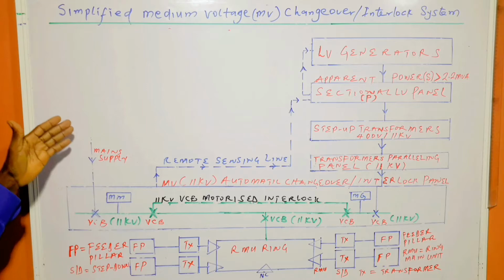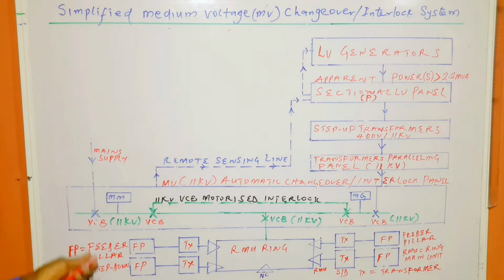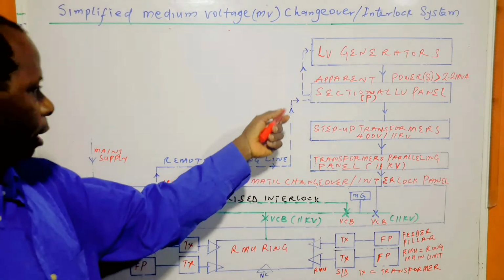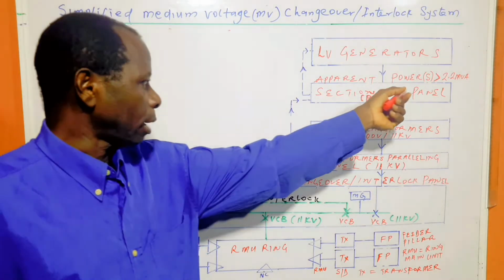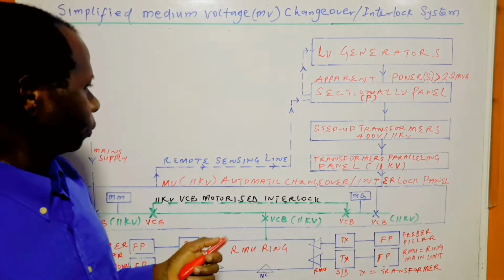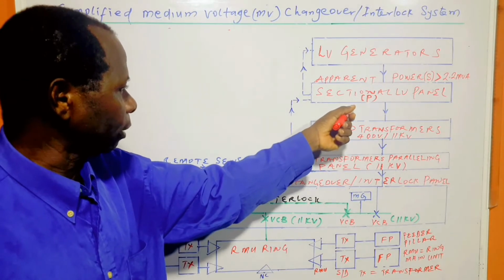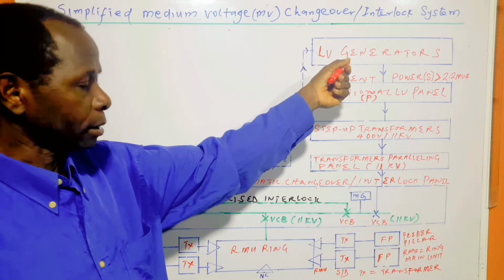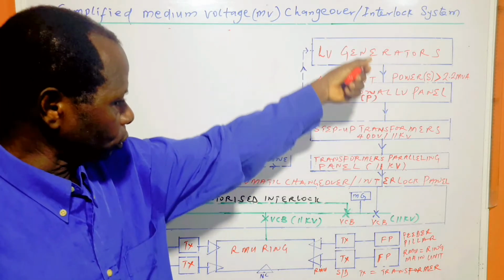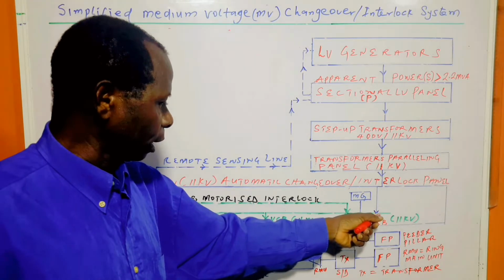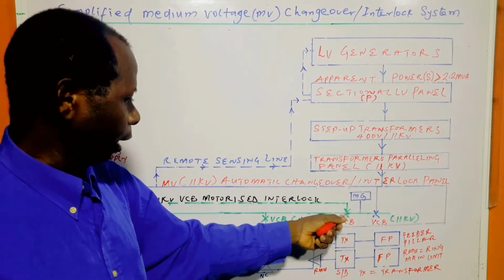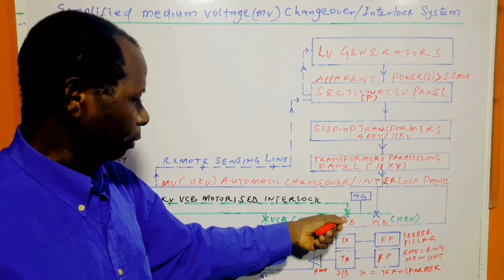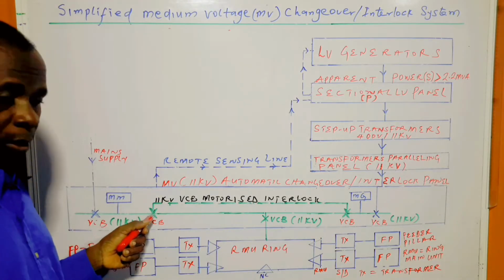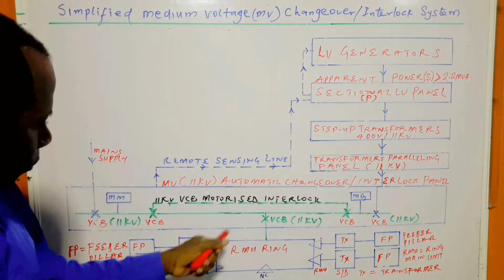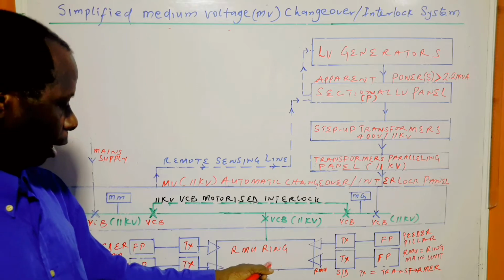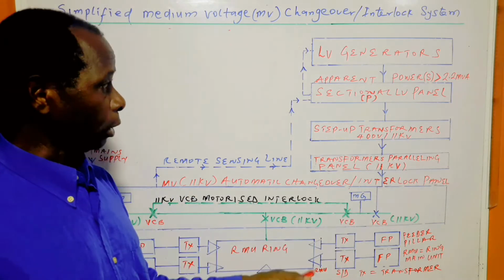And what happens is that immediately there is power interruption, this panel sends a signal through this remote sensing line to this sectional LV panel P, and this LV panel P signals the generators to start. So the generator will start and continue to supply power to the load through this vacuum circuit breaker. And when the power is delivered to this place, this circuit breaker closes and this one opens. With that, power is able to reach this RMU ring and also the load.